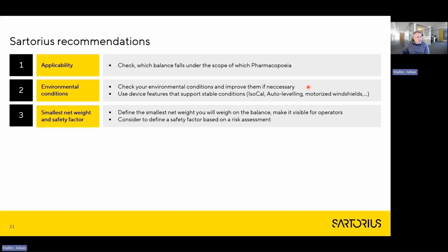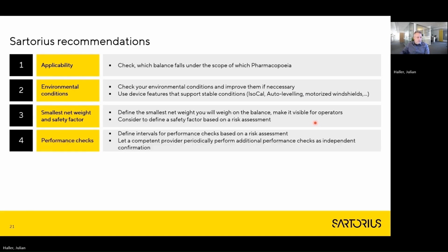Concerning the smallest net weight and the safety factor, we recommend to define the smallest net weight that you will weigh on the balance and make it visible for operators, for example, by placing a respective label on the balance. Consider to define a safety factor based on a risk assessment. Concerning the performance checks, we recommend to define intervals for the performance checks based on a risk assessment and to let a competent provider periodically perform additional performance checks, additional to your own performance checks, as independent confirmation.